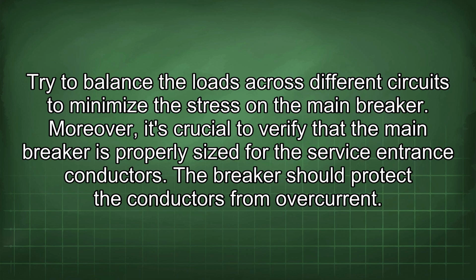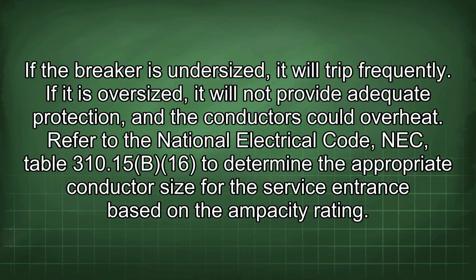Moreover, it's crucial to verify that the main breaker is properly sized for the service entrance conductors. The breaker should protect the conductors from overcurrent. If the breaker is undersized, it will trip frequently. If it is oversized, it will not provide adequate protection and the conductors could overheat. Refer to the National Electrical Code, NEC Table 310.15(B)(16), to determine the appropriate conductor size for the service entrance based on the ampacity rating.